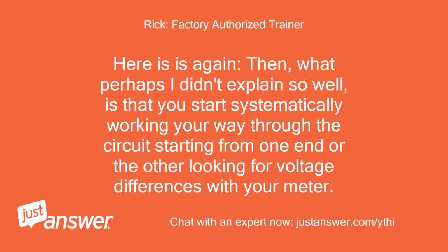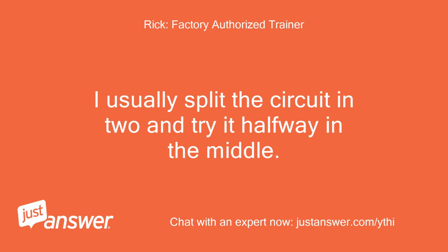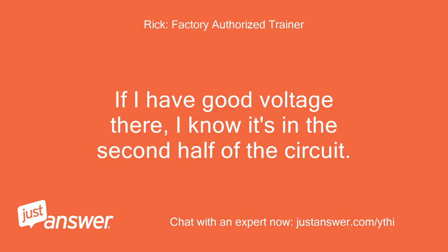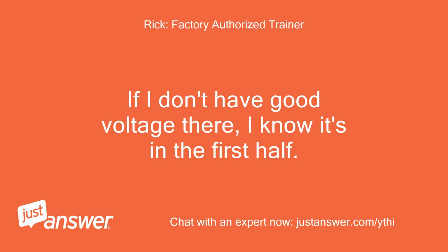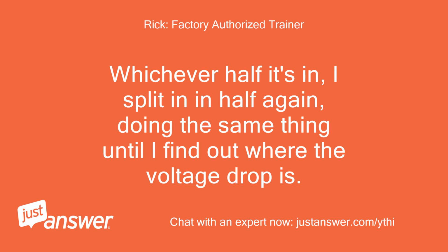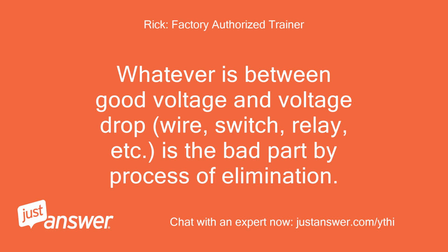the circuit starting from one end or the other looking for voltage differences with your meter. I usually split the circuit in two and try it halfway in the middle. If I have good voltage there, I know it's in the second half of the circuit. If I don't have good voltage there, I know it's in the first half. Whichever half it's in, I split it in half again, doing the same thing until I find out where the voltage drop is. Whatever is between good voltage and voltage drop, wire, switch, relay, etc., is the bad part by process of elimination.